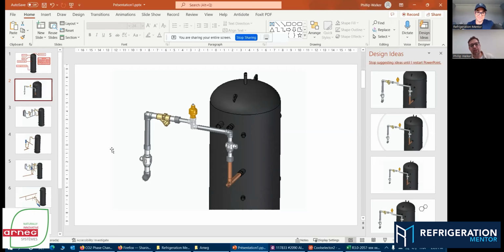This is critical. Remember, everything coming down on your stainless steel line, or maybe your K65 line, depending where you are in North America, is coming down, slamming into this valve. So we're talking, what type of velocities are you guys thinking of? Well, slamming is the right word. We typically will not exceed 500 feet per minute coming down here as my run. Remember, you've got 1 valve or maybe 2 valves here. It could be the Carel, the Danfoss, the Parker model. Regardless, they're all operating in a very similar fashion, fine-tuned differently for each one. But we've got to respect that valve. The cleaner we keep that valve, and it has a strainer here, the better it's going to run. Don't forget, this valve is probably the second most important part in your system. The first being the temperature sensor that controls it.